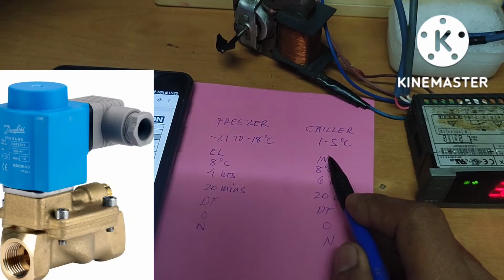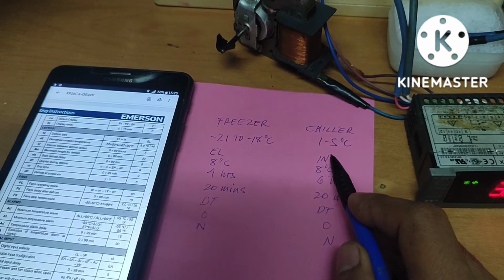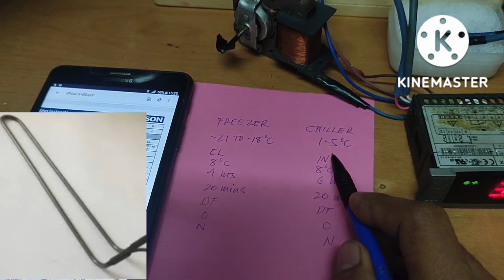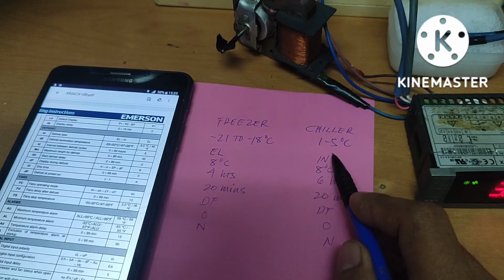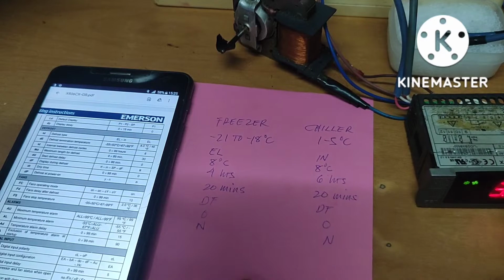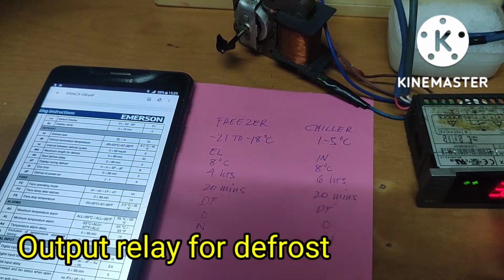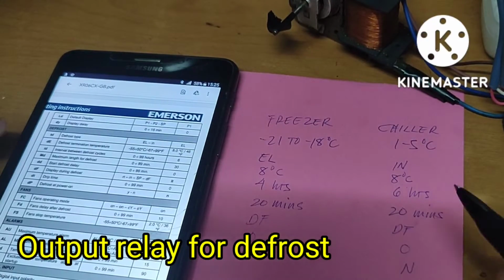is the hot gas, but in most cases a chiller doesn't have a defrost heater, so what they set there is time defrosting or fan defrosting. But since this is an XR06CX, it has a parameter for the defrost heater.